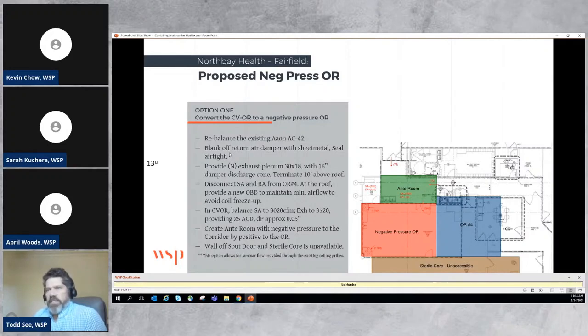North Bay had gotten out ahead of this process by talking to the California OSHPD. The OSHPD process typically takes about 80 days for their initial review. They allow 90 days for design team response and 40 days for their back check, and then that becomes an iterative process. So with the time those reviews typically take, North Bay had reached out to OSHPD and said, how can we work together? And OSHPD had agreed that temporary measures could be put in place as long as everything met code. They weren't going to go through the formal OSHPD review process.